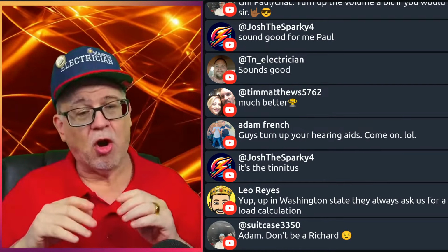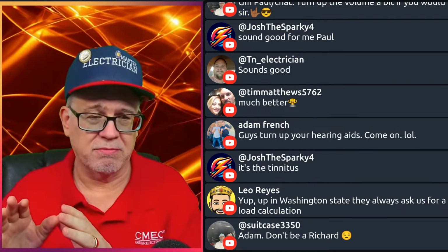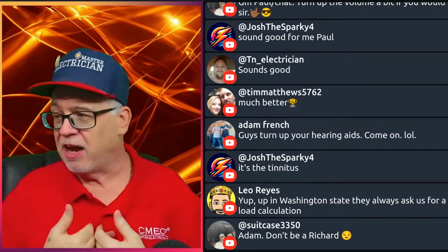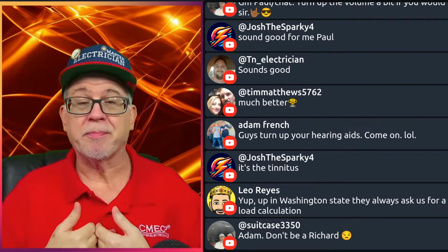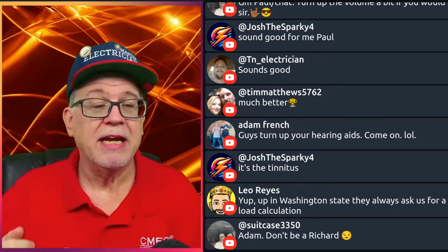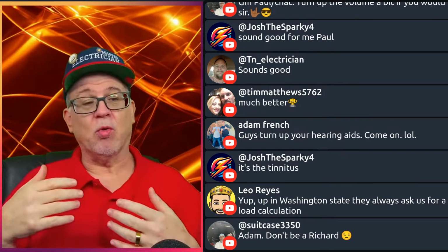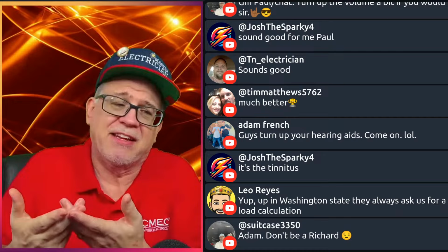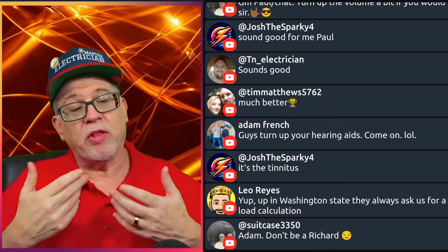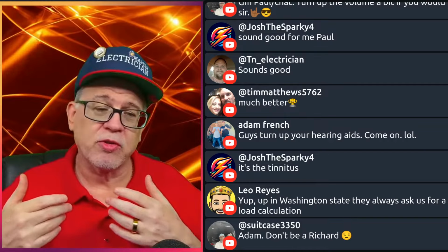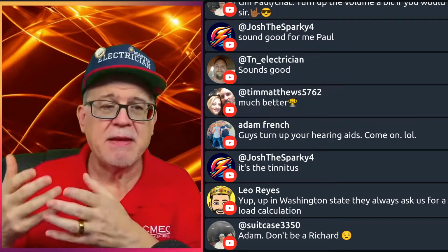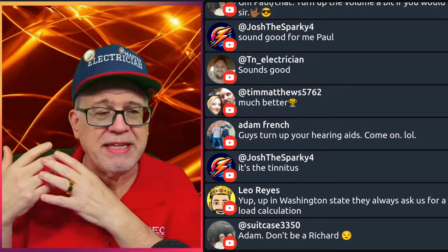So right now, all you do is write those numbers down. We're not ready to apply any demand yet, because now we have to go through and simply get the nameplates. And that's why I tell you guys in the real world, it's so much easier. Even if I've got an existing service and I'm going to be adding something to it, and I want to know whether I've got headroom on it, all I have to do is go to the appliances that have the nameplate and take the values from the nameplate.